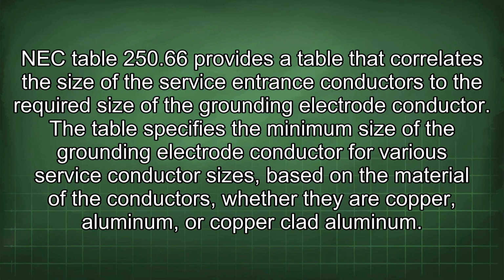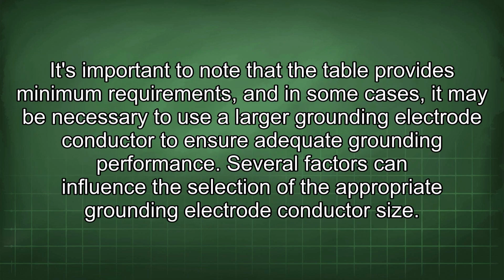NEC Table 250.66 provides a table that correlates the size of the service entrance conductors to the required size of the grounding electrode conductor. The table specifies the minimum size of the grounding electrode conductor for various service conductor sizes based on the material of the conductors, whether they are copper, aluminum, or copper-clad aluminum. It's important to note that the table provides minimum requirements, and in some cases, it may be necessary to use a larger grounding electrode conductor to ensure adequate grounding performance.